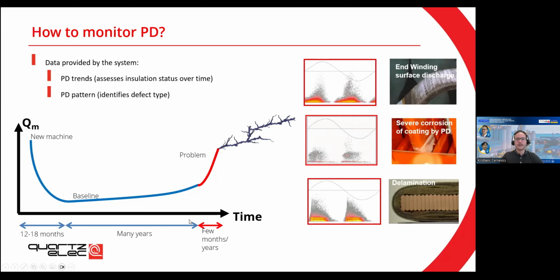However, there's going to be a point in time where there's going to be a problem with the machine. And what will happen is that in only a few months, maybe a couple of years, these discharges will grow very fast. This is the point where you need to catch the condition of your machine before the problem gets very, very bad. If there is no condition monitoring and, for many years, everything has been right, you reach this point and you don't capture that the PD discharges are now happening much, much more, and you don't see it because maybe your maintenance only happens once or twice a year. So that's another reason why condition monitoring is necessary to help your asset health.